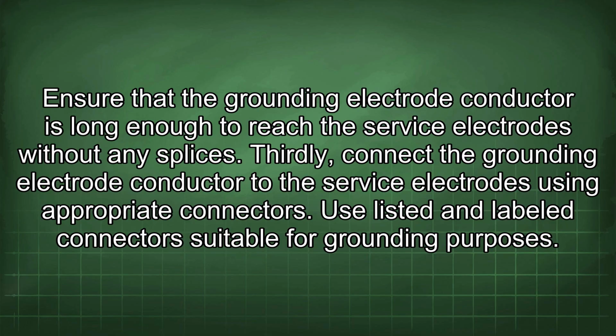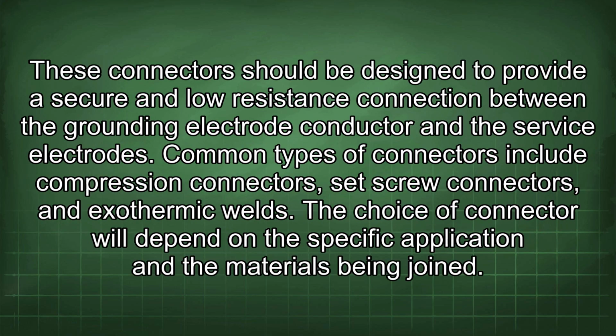Thirdly, connect the grounding electrode conductor to the service electrodes using appropriate connectors. Use listed and labeled connectors suitable for grounding purposes. These connectors should be designed to provide a secure and low resistance connection between the grounding electrode conductor and the service electrodes. Common types of connectors include compression connectors, set screw connectors, and exothermic welds. The choice of connector will depend on the specific application and the materials being joined.